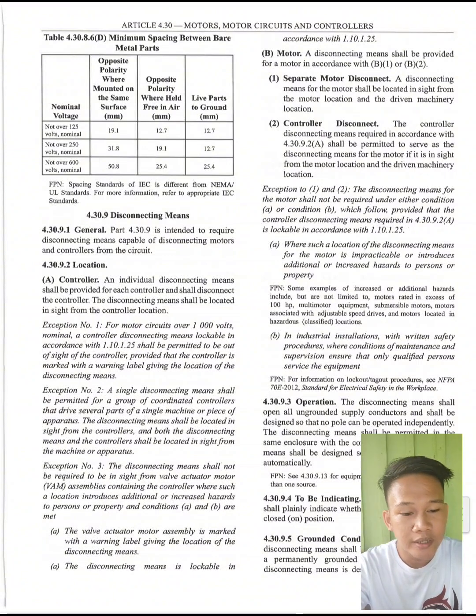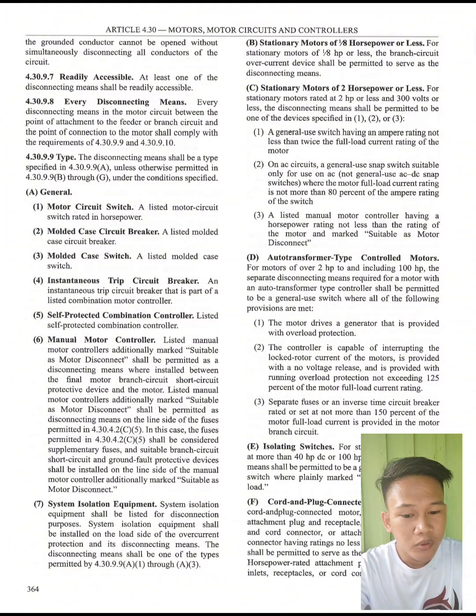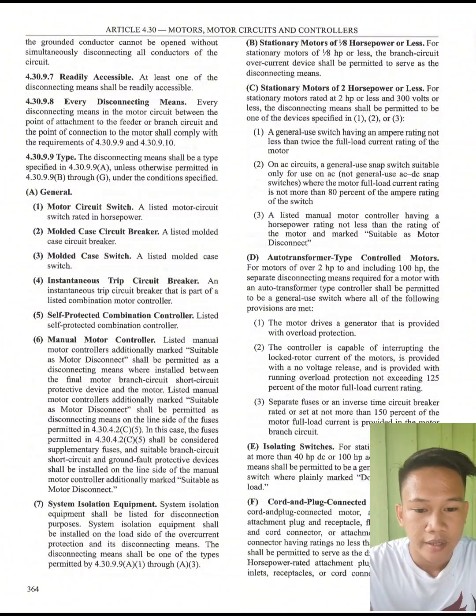So next is 4.30.9.5 grounded conductors. One pole of the disconnecting means shall be permitted to disconnect a permanently grounded conductor, provided the disconnecting means is designed so that the pole in the grounded conductor cannot be opened without simultaneously disconnecting all conductors of the circuit. Next, we have 4.30.9.7 readily accessible. At least one of the disconnecting means shall be readily accessible.